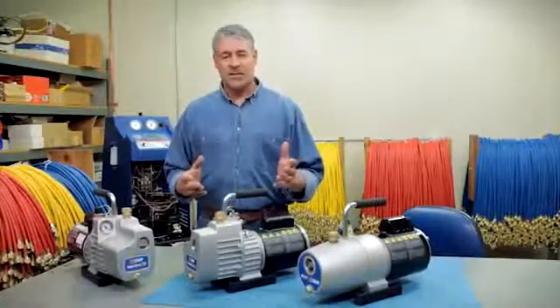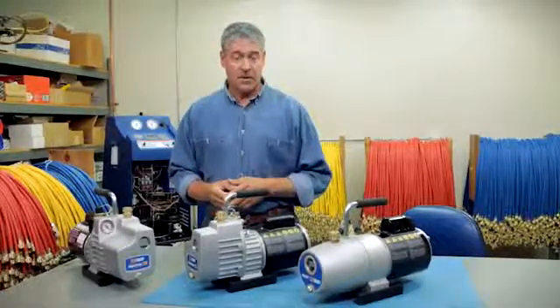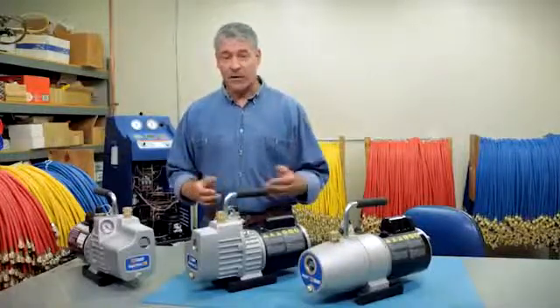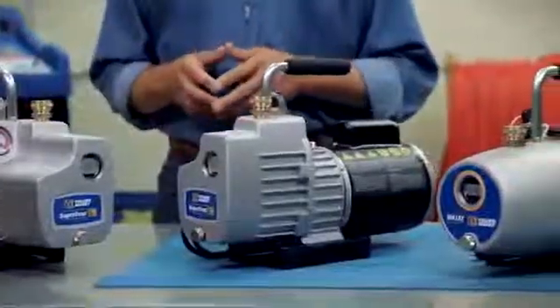Most air conditioning systems today require a critical charge for optimal operation. This makes them very sensitive to moisture and other contaminants, which can freeze up the system, corrode the metals, and sludge the oil, the cause of most problems and complaints when a system stops working. Therefore, it's extremely important to remove moisture with a quality vacuum pump before the critical charge takes place.